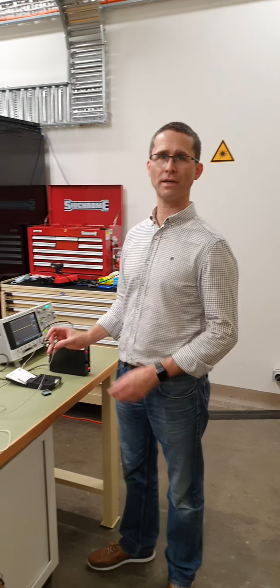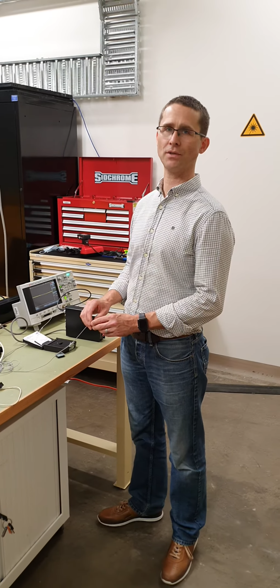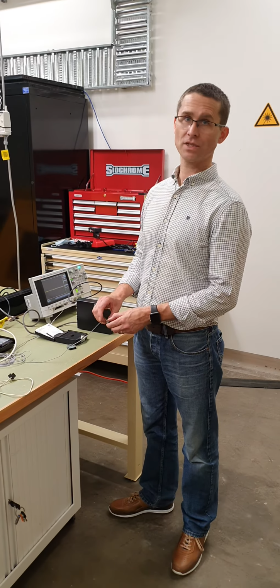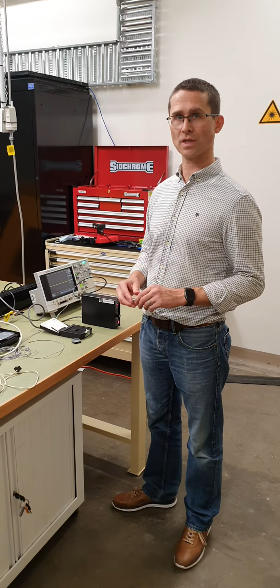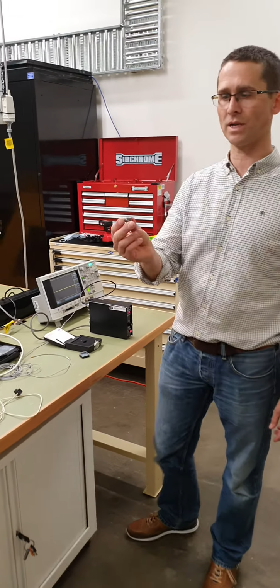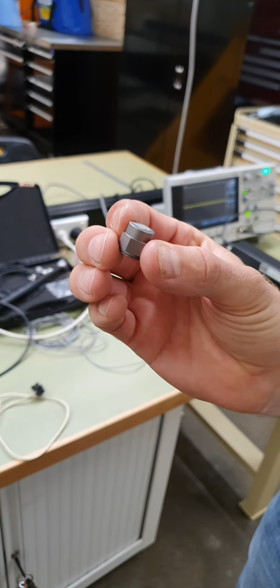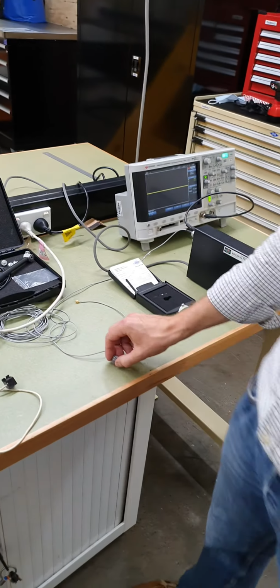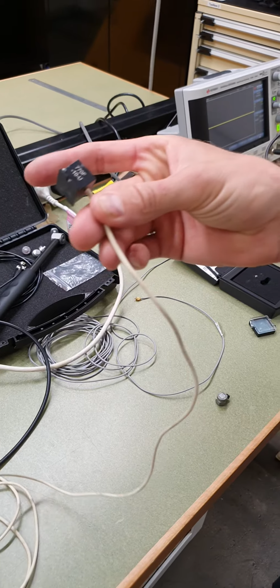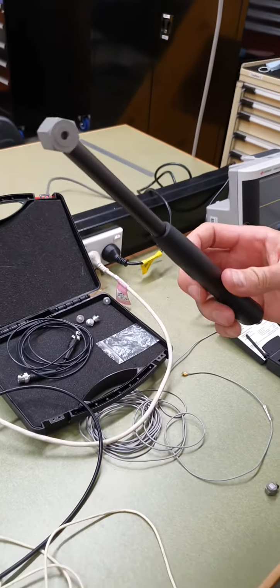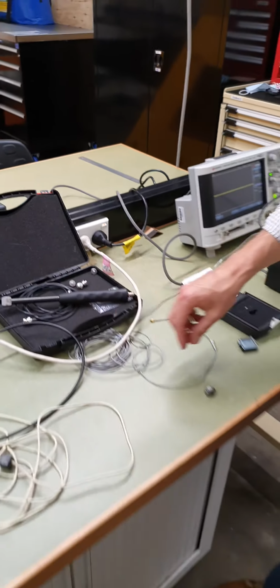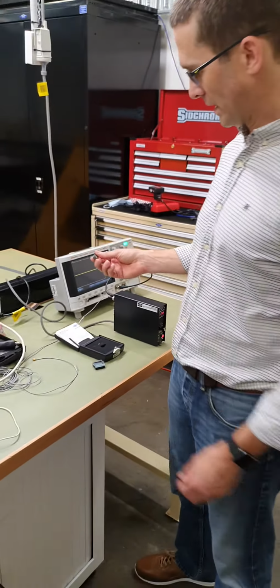I'm a senior lecturer here in the School of Mechanical and Electronic Engineering at UTS, and this is the Vibration Lab. This video is to introduce the use of various different types of transducer that we use for measuring vibration. For example, this single axis accelerometer here, which is a device from Brüel & Kjær, a 4353B transducer. There are different types of transducer, like this microelectromechanical system transducer here, a different type. We also have impact hammers, which are force transducers, essentially, and are similar in principle of operation to an accelerometer.